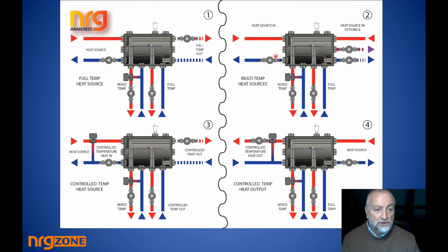You do not have to go by any one of the pipe examples I'm showing, because each of them are different and independent in their own right, and have their own reasons why they're better in certain circumstances. So there is no fixed rule except that you take from the chamber you feed into with hot water and with return water. Now in this scenario, so we have a mixed temperature zone on A1, A2 and a full temperature zone on B1, B2.